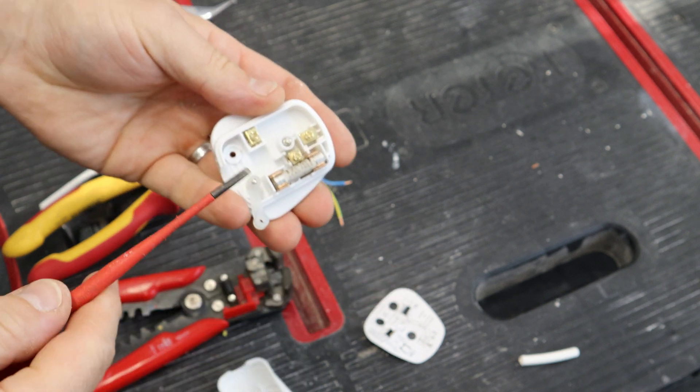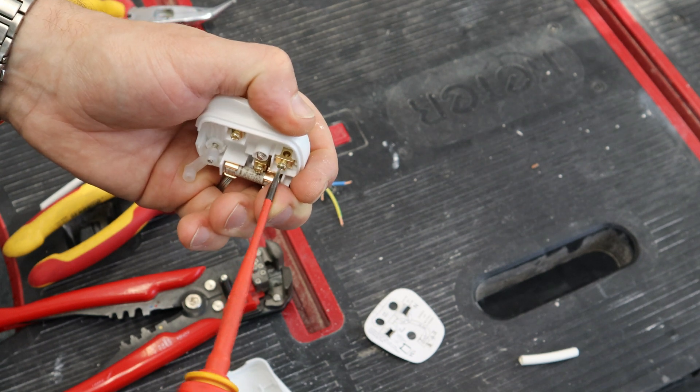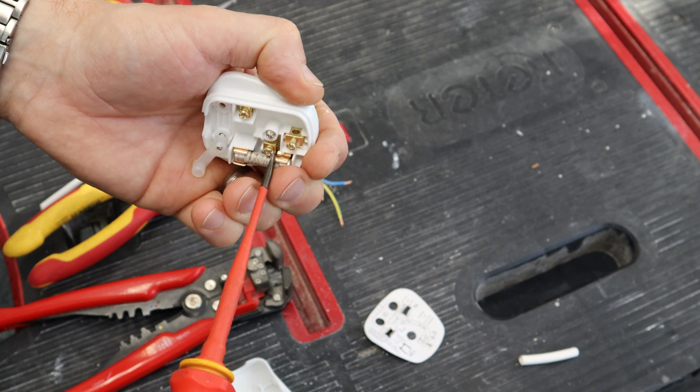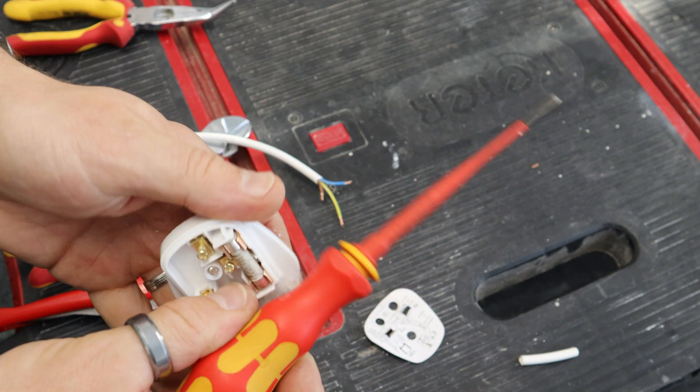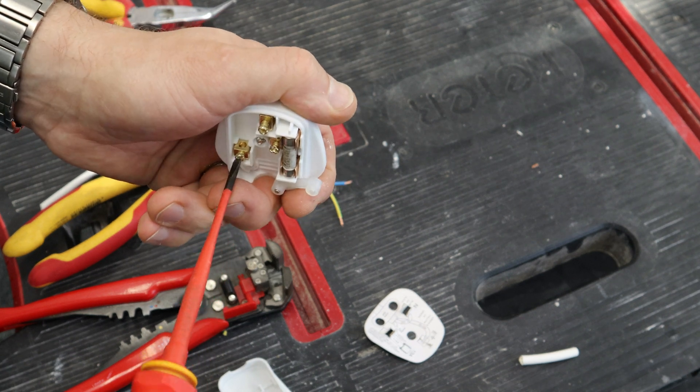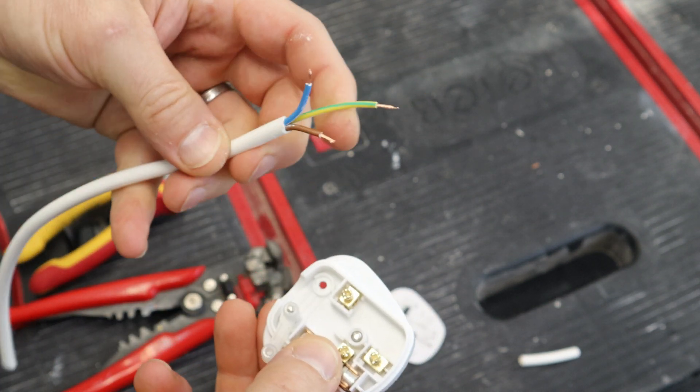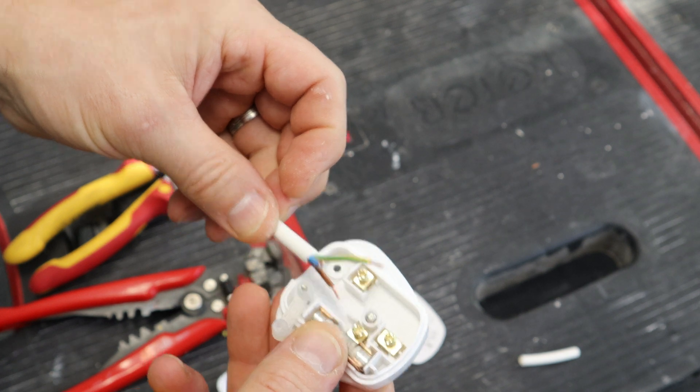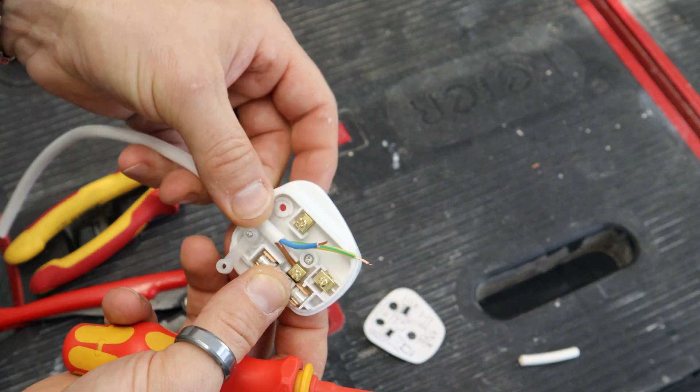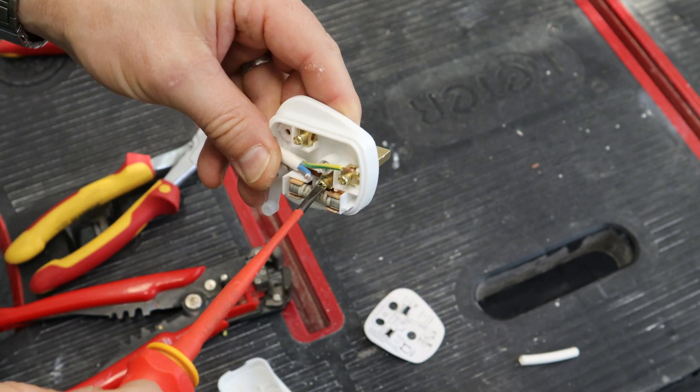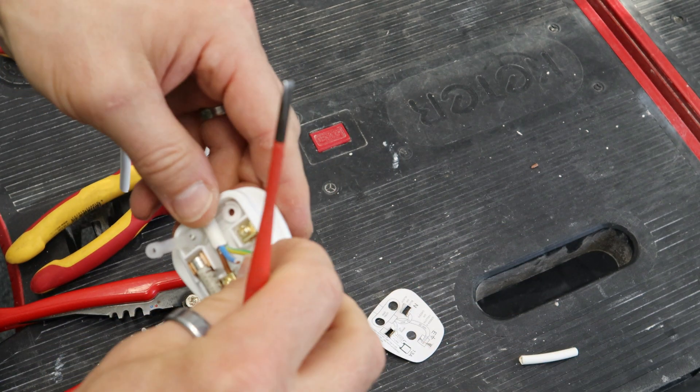Like so. So here we have the live, neutral, and earth. So we just have to undo the grub screws. Take it almost all the way, but obviously don't take them all the way out. Do this for all three. Now taking your cable, generally easier to start with the live. And just slide it in. And then do it up. Don't over tighten them, but at the same time give it a little tug, just to check that it fits okay.